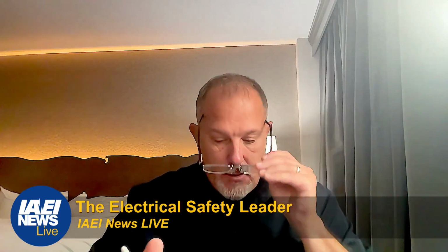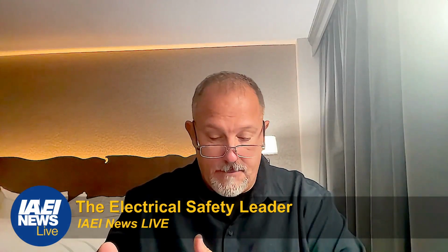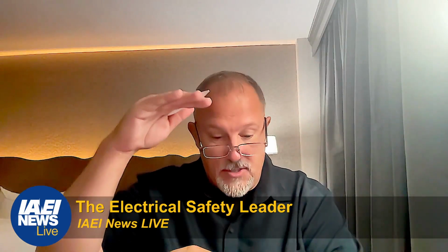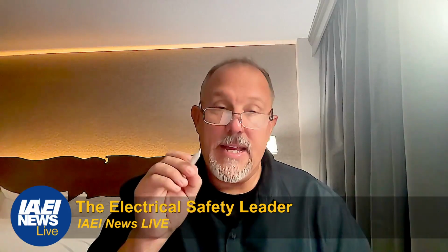And then what we compromised on was that you're not required to put a receptacle on an island or peninsula. But if you do, it has to be on the top. You can't put it below the countertop. So the way we said this, we said receptacle outlets, if installed to serve an island or peninsula countertop or work surface, shall be installed in accordance with 210.52(C)(3), and then we'll talk about the receptacle outlet location. If a receptacle outlet is not provided to serve an island or peninsula countertop or work surface, provisions shall be provided at the island or peninsula for future addition of a receptacle outlet to serve the island or peninsula countertop.